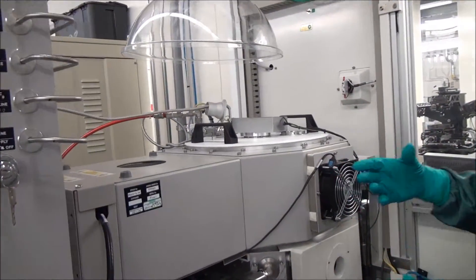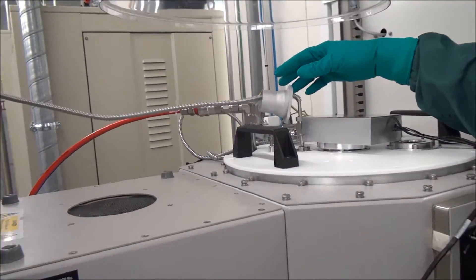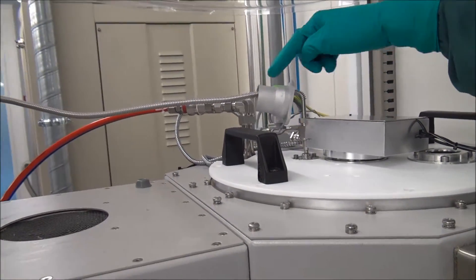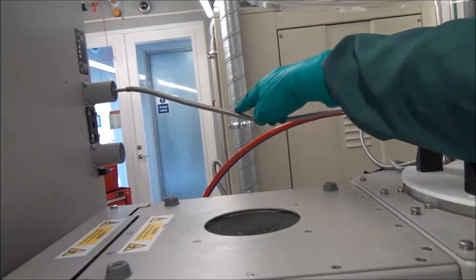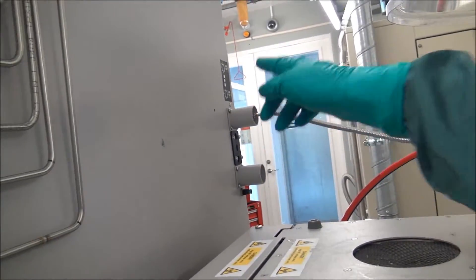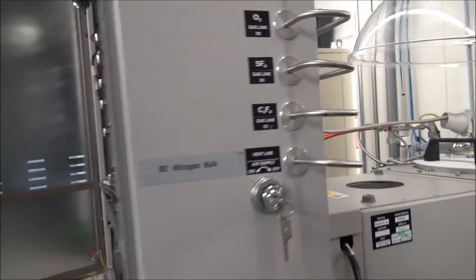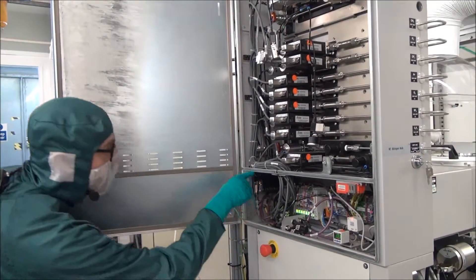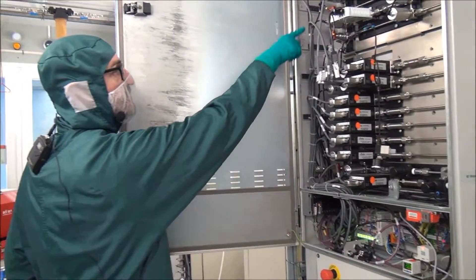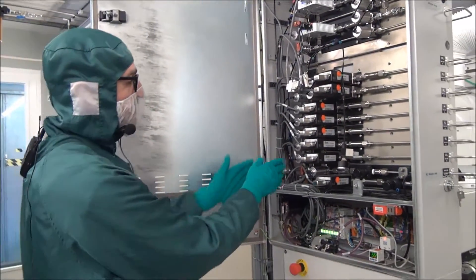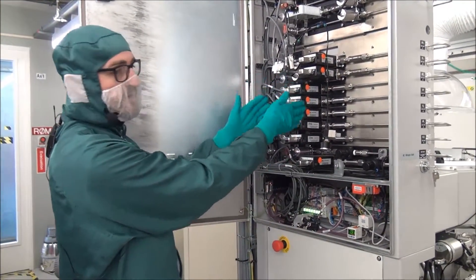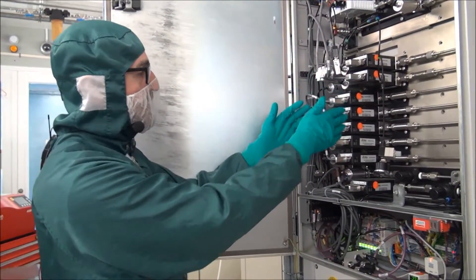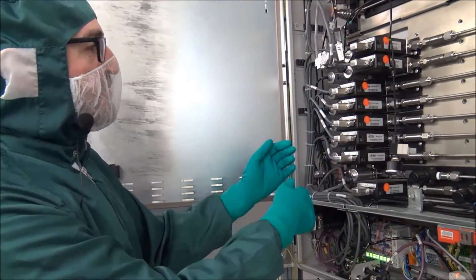If we go back to the top again I would just like to show you where the gases are coming in. So we have this is the main gas inlet pipe. So we follow the line here. Let me go and look inside. So the gas actually comes in on this manifold here. So we have some mass flow controllers for all the different gases, and this is what you control in your program. You set the flow and hopefully it will go to the correct value.